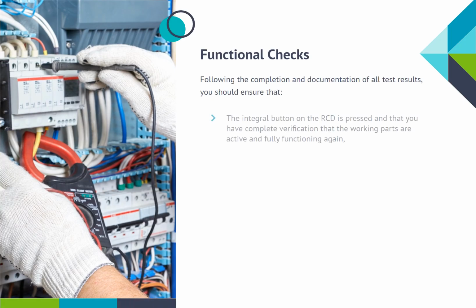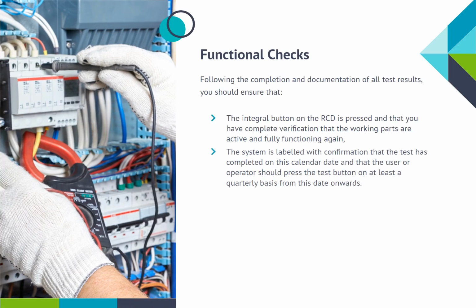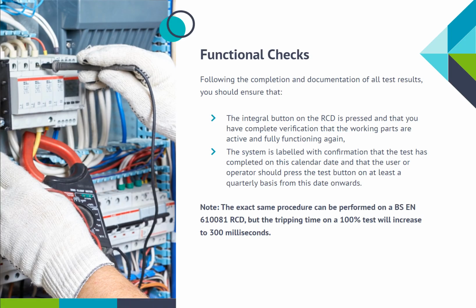Following the completion and documentation of all test results, you should ensure that the integral button on the RCD is pressed and that you have complete verification that the working parts are active and fully functioning again. The system is labeled with confirmation that the test has completed on this calendar date, and that the user or operator should press the test button on at least a quarterly basis from this date onwards.